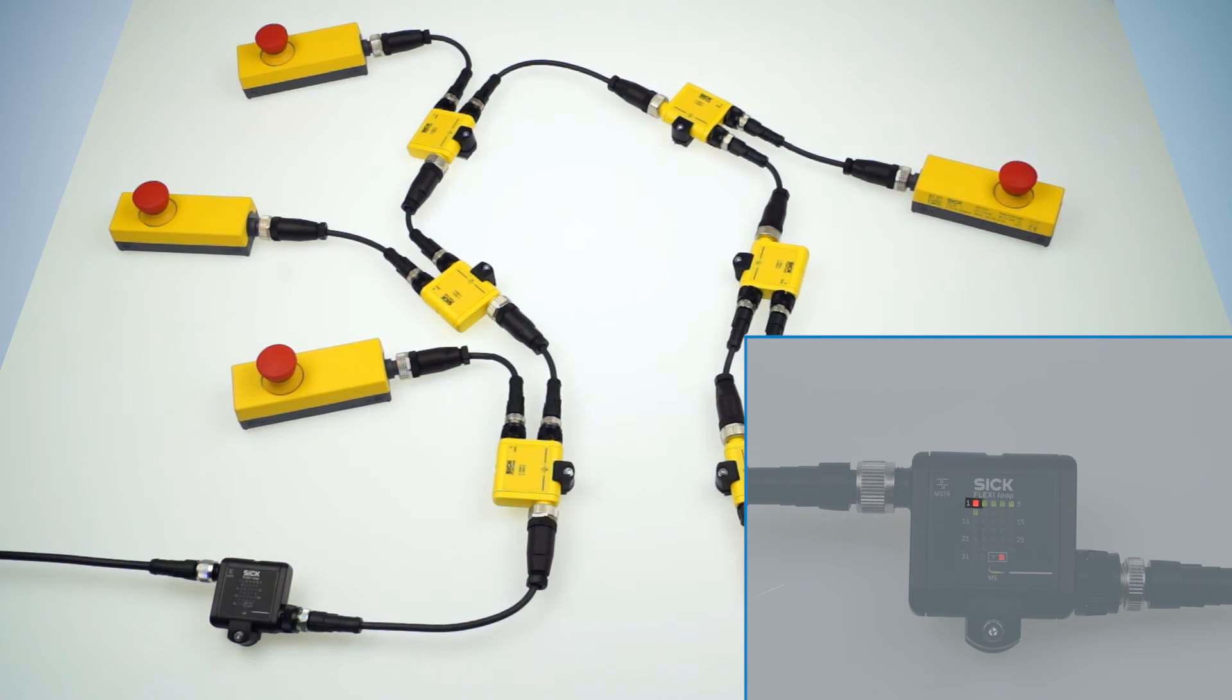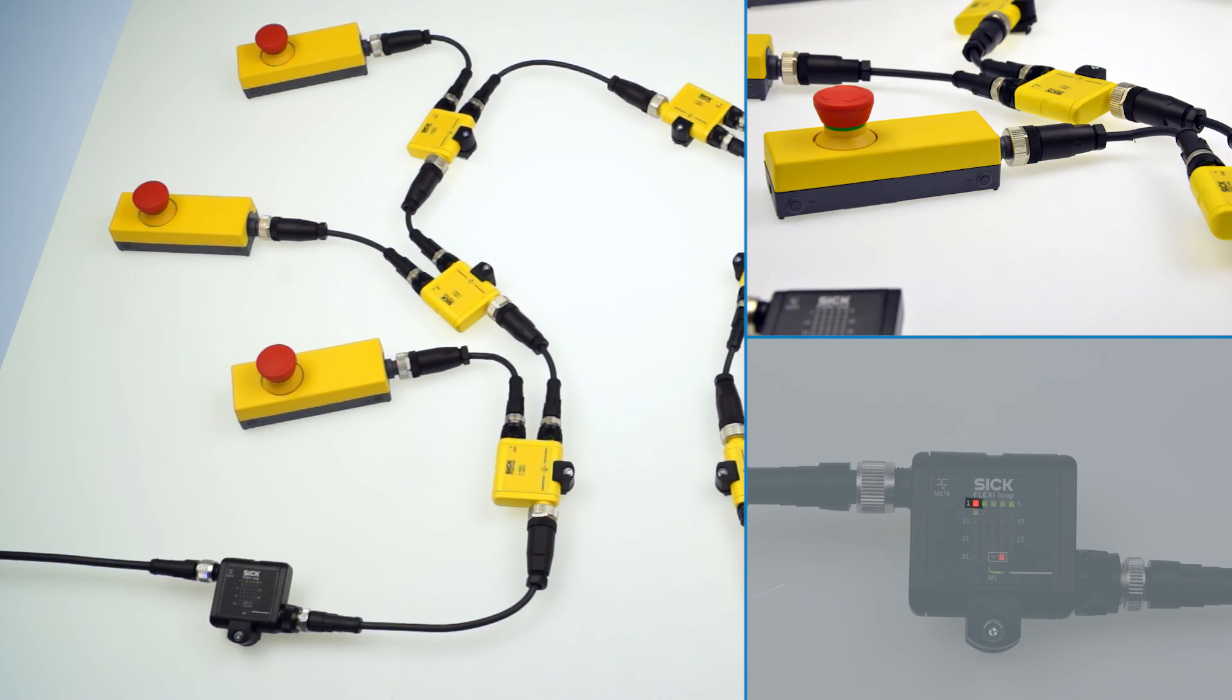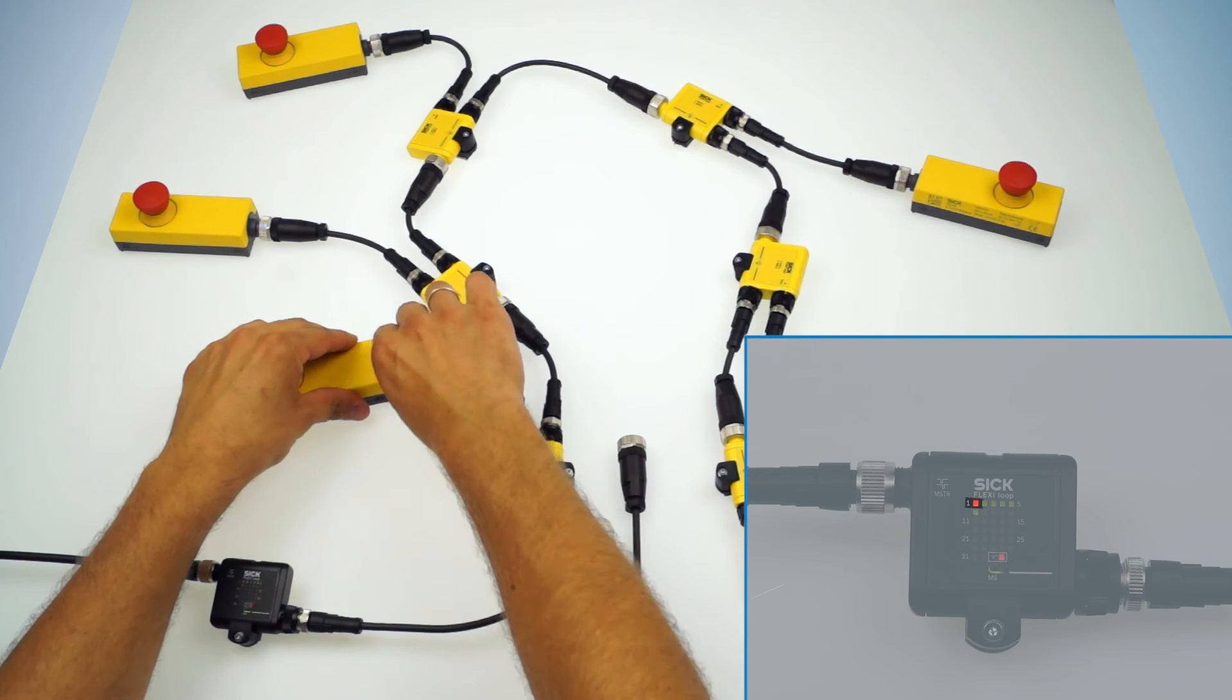And Node LED 1 is flashing red. So a discrepancy error occurred. By checking the sensor and the cabling we are easily able to figure out that there is a cable break. So we just need to change that.